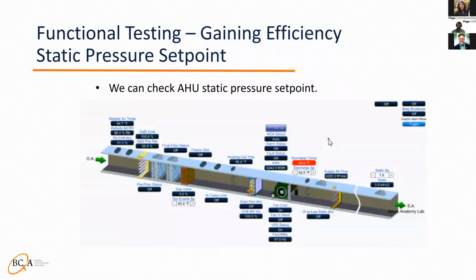Since you've already driven the system into full cooling, at this point you might as well check the static pressure set point. This may require some further manipulation if there is diversity, but the system should still settle out faster if it is done now rather than later when testing the AHU.